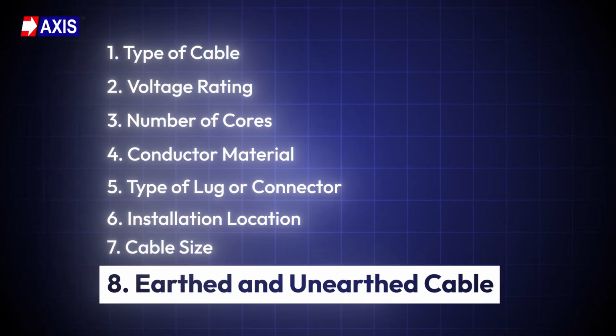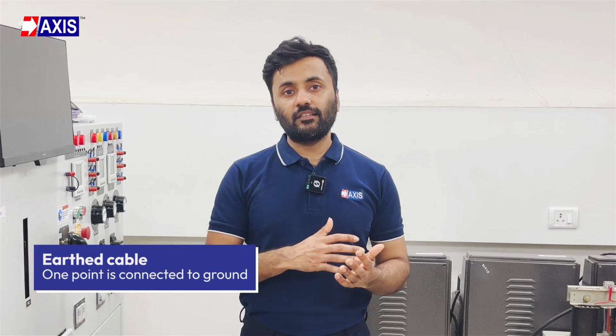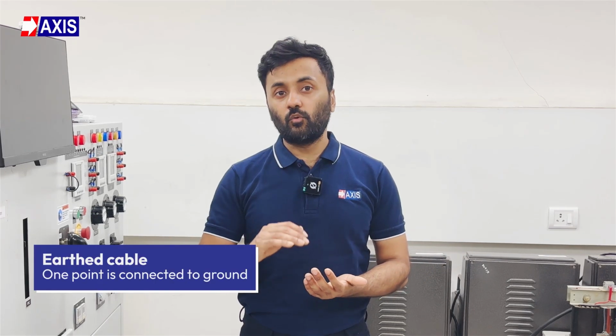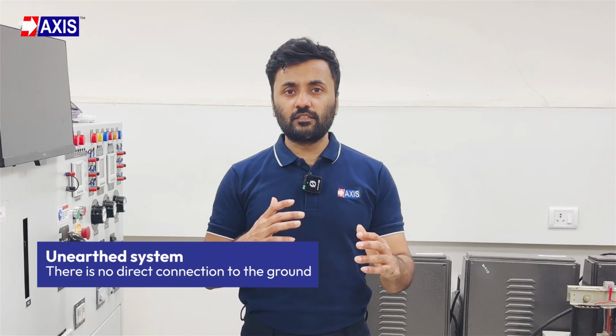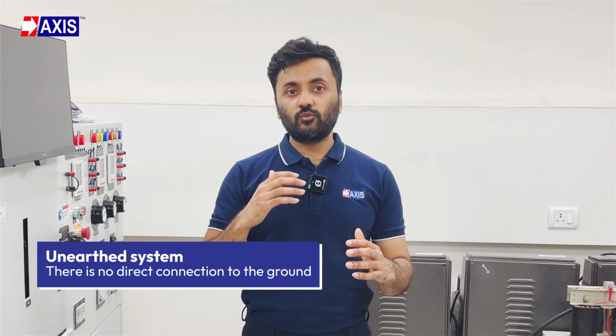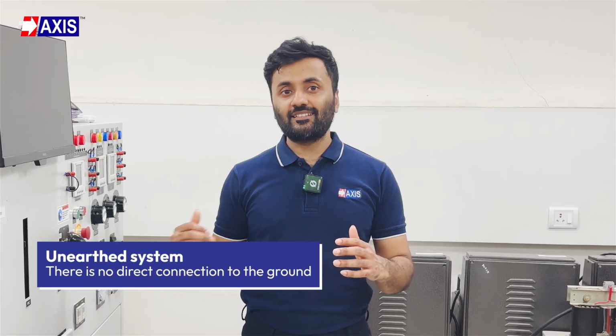Number 8. Earthed and unearthed cables. Check whether your cable is earthed or unearthed. In an earthed system, one point is connected to the ground, which helps control overvoltage. In an unearthed system, there is no direct connection to the ground, so the insulation faces higher stress during faults. Because of this difference in electrical stress, the insulation requirement changes.